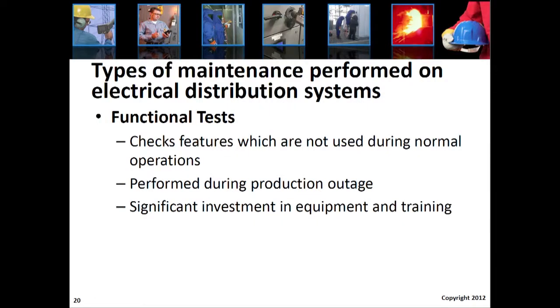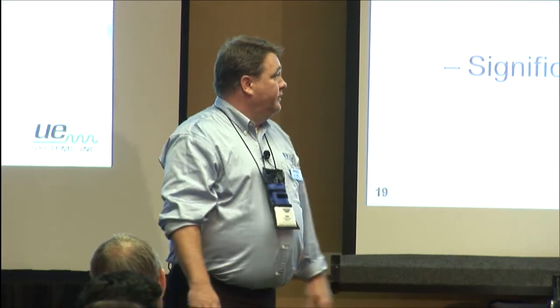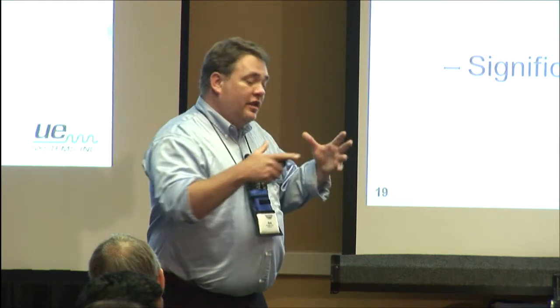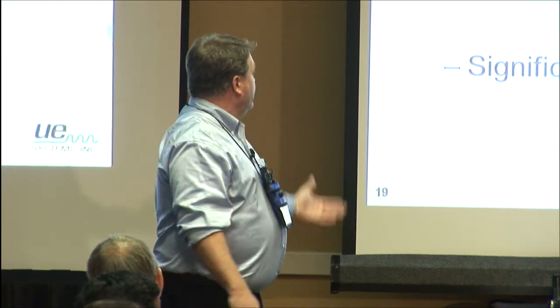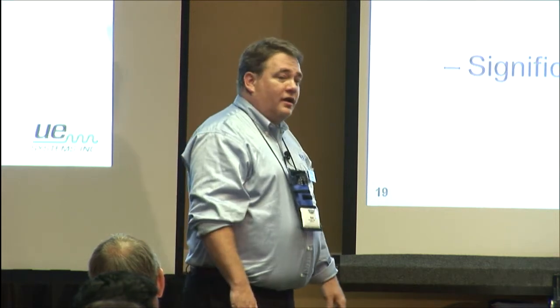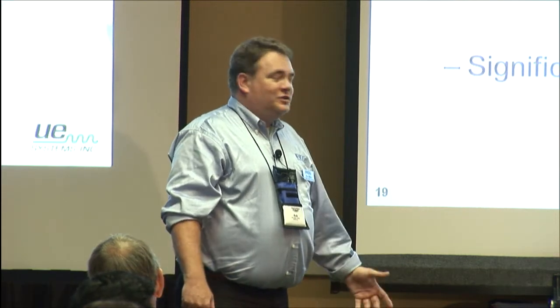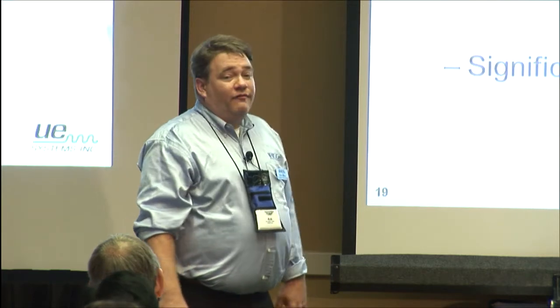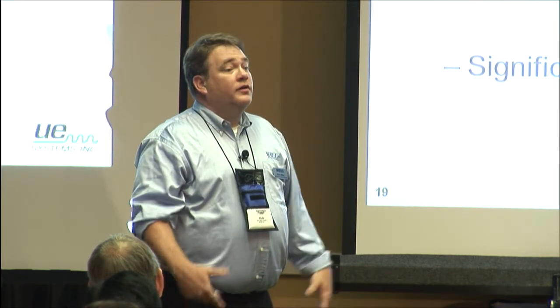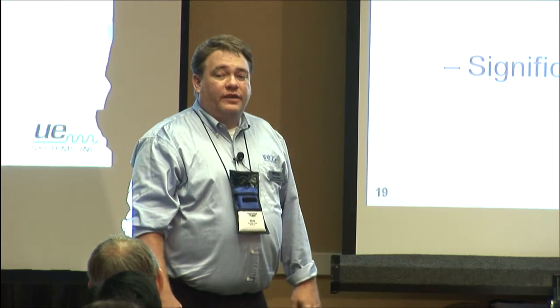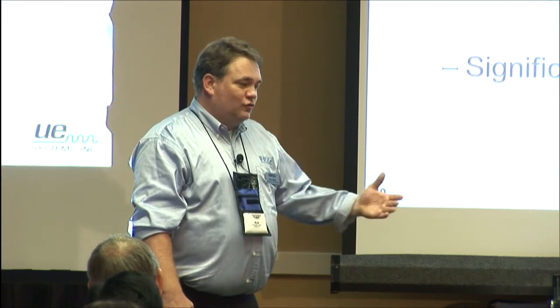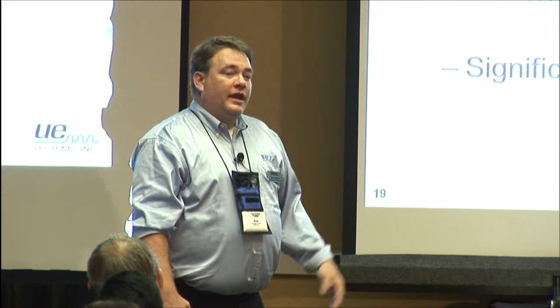Functional test covers things that don't necessarily get used during normal operation. The overload that trips out a 2,000 amp breaker, you don't really want to functionally test in production, but there's plenty of people out there that will come and do that, so you do it on a regular basis. When it's not actually in production you can simulate that, usually done during an outage, which makes it hot and sweaty and tends to be expensive. You get a big investment in the equipment and training, or in a third-party contractor that comes out and does it, involving their own training and personnel, so you pay a premium for that.